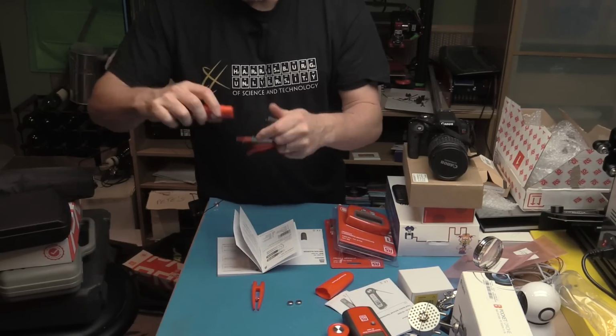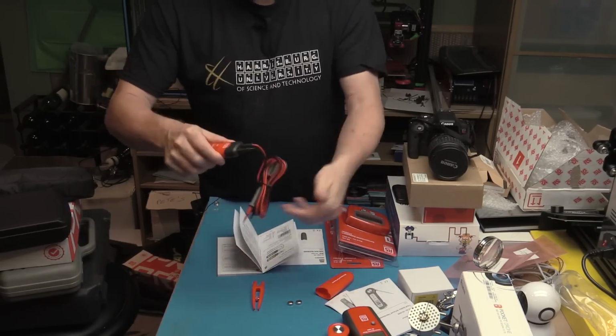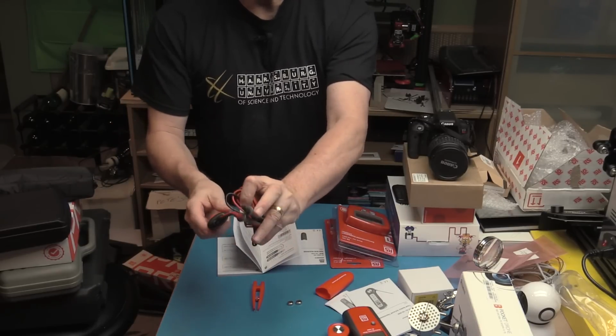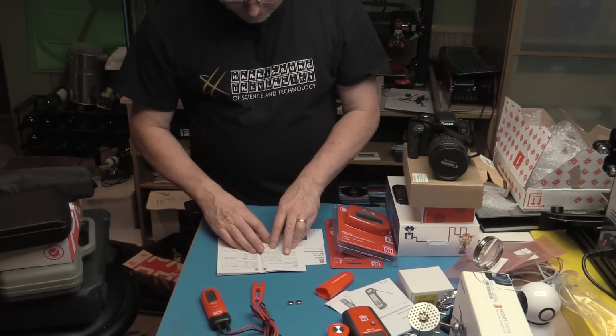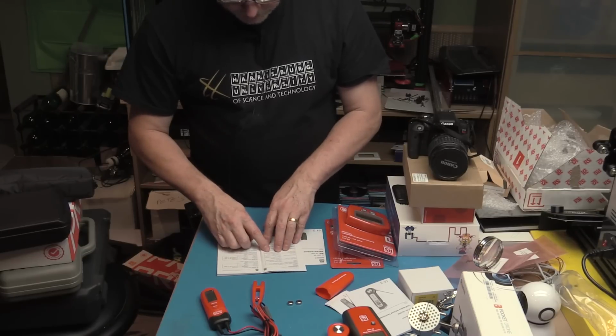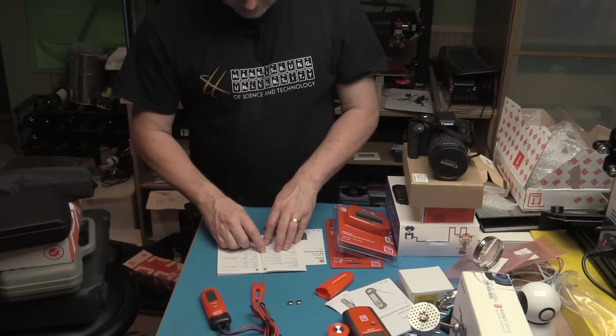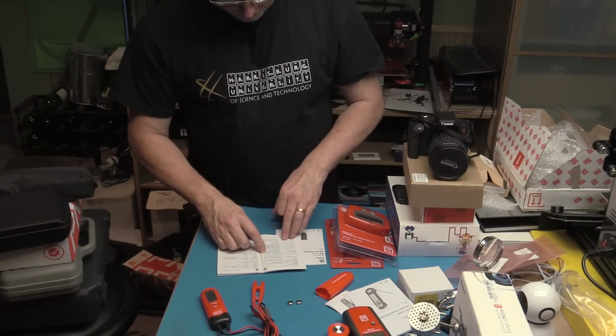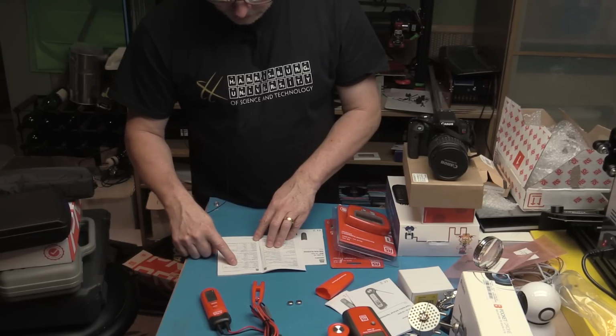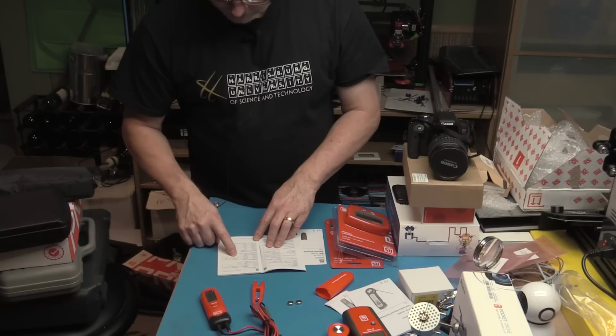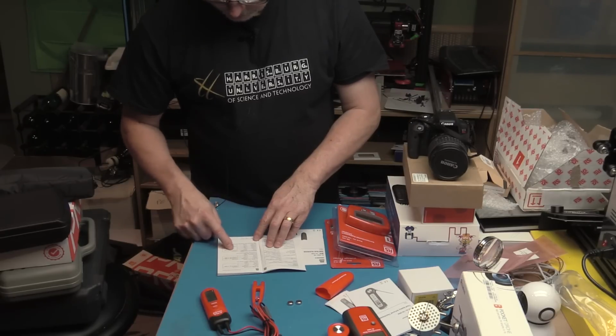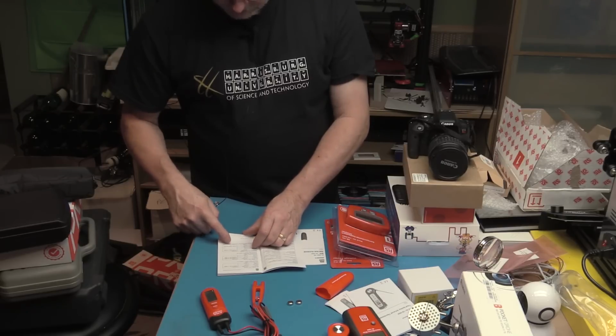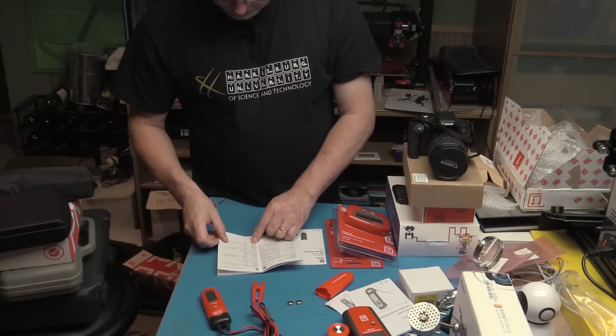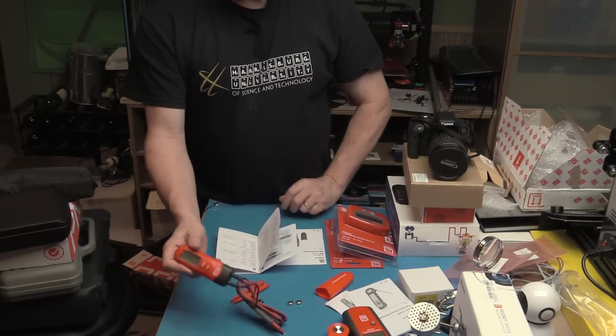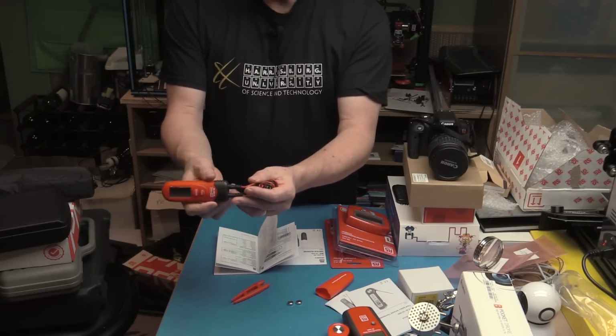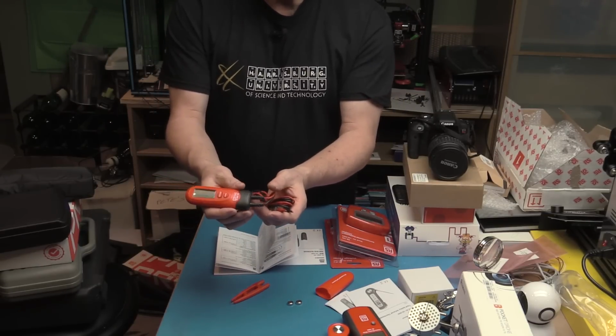Did I get that the right way around? No, I did not. There we go. So that you can use just standard test probes as well to measure something. So look, does it say two samples per second? Batteries will last about 60 hours of use. Auto power off, 0.5% accuracy on DC voltage, AC voltage 0.8% of reading. Resistance about 1%, 1.5%, 2.5% for the high 60 megohm range. So very basic test component, voltage tester and things like that.